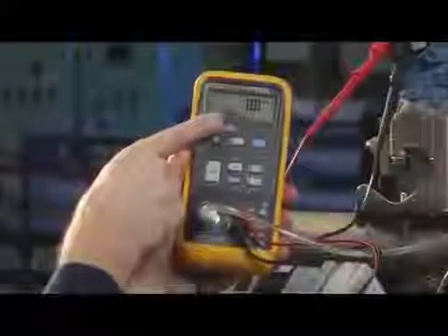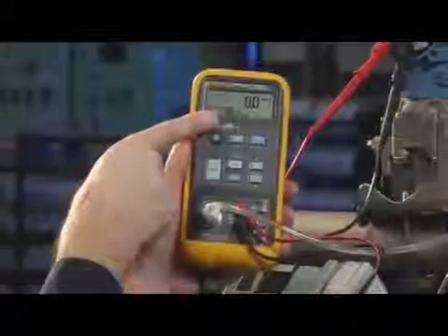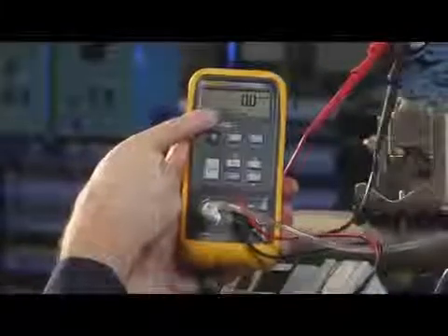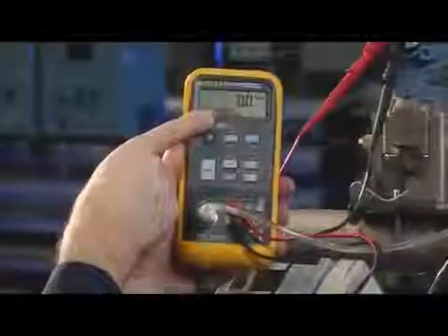This pressure vacuum switch allows you to pump either positive pressure or negative pressure. For this example we're going to measure positive pressure. First we apply 0 inches of water, measure 4 milliamps. Any deviation from 4 milliamps is calibration error.